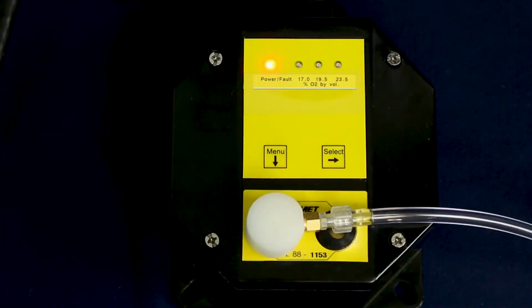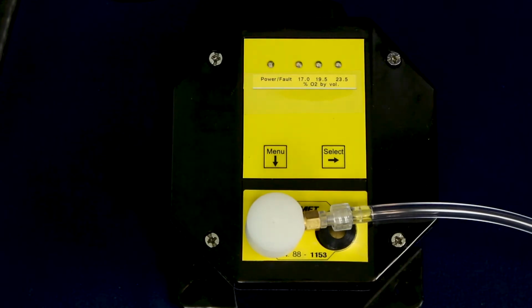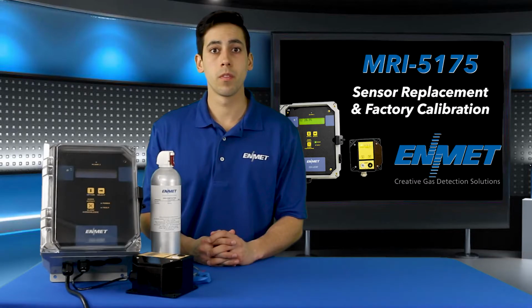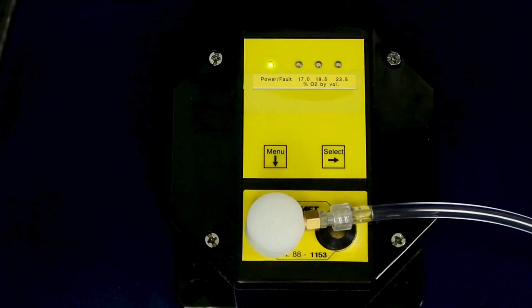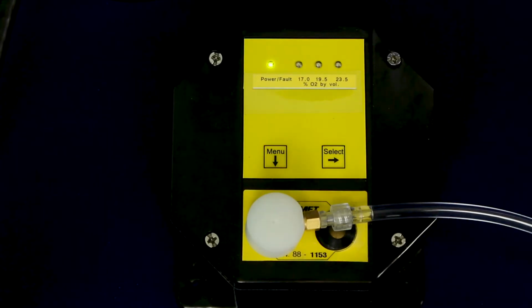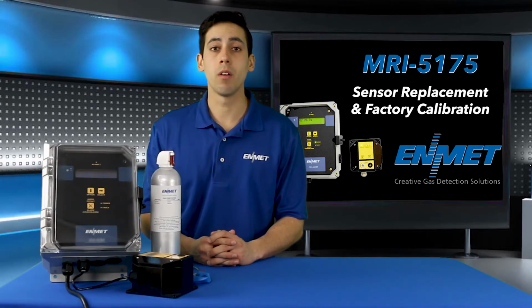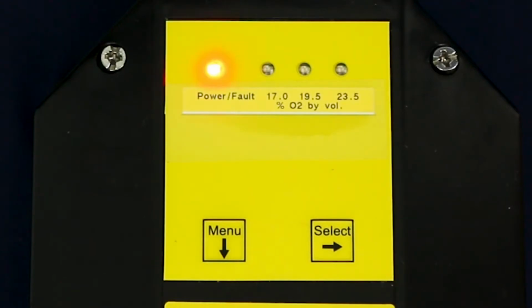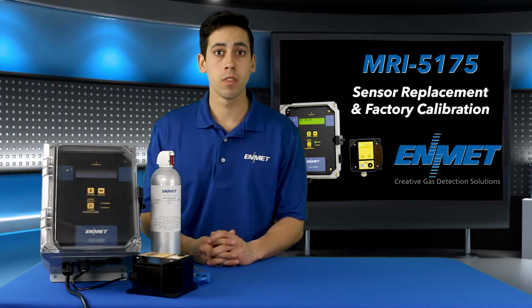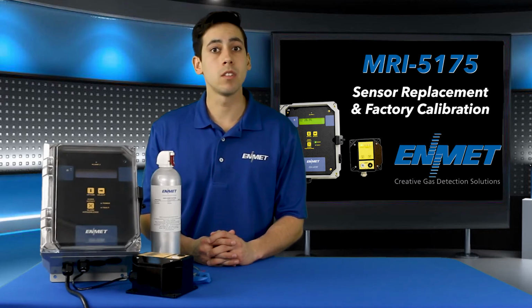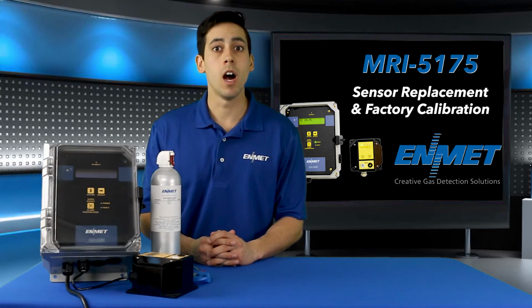Press and release the select switch to exit the calibration and return to the operational mode. If the calibration was completed successfully, the power fault LED will show a steady green. If the calibration failed, the power fault LED will show red, green on repeat. If this happens, consult ENMET technical support for help. This completes the sensor replacement and the factory calibration of ENMET's MRI 5175 oxygen sensor transmitter for MRI installations.